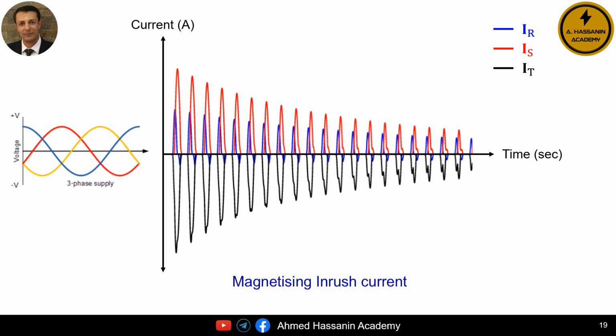Of course, the difference in the shape and value of the magnetizing inrush current for each phase occurs because, as we know, at any given moment, there will be a difference between the voltage values of phase R, phase S, and phase T. Since there is a difference in the voltage for each phase, it means that there will also be a difference in the magnetizing inrush current for each phase.